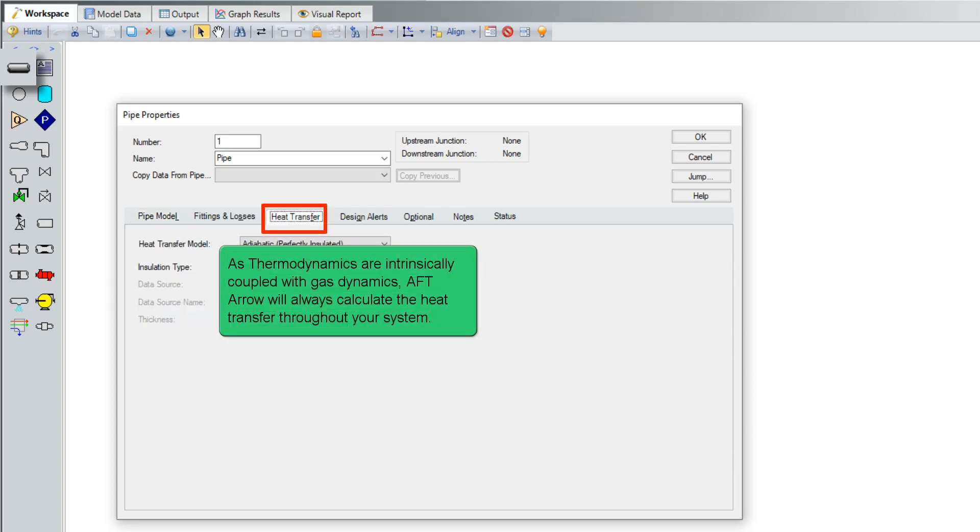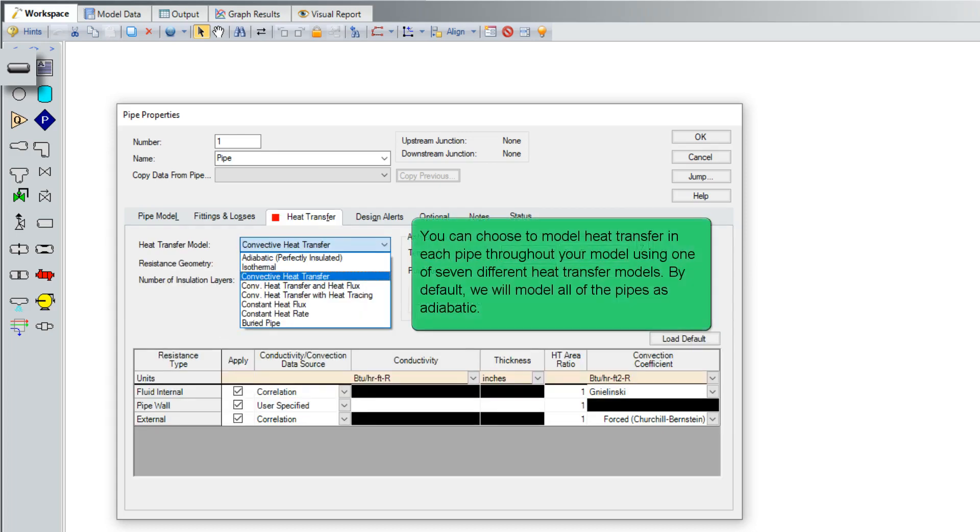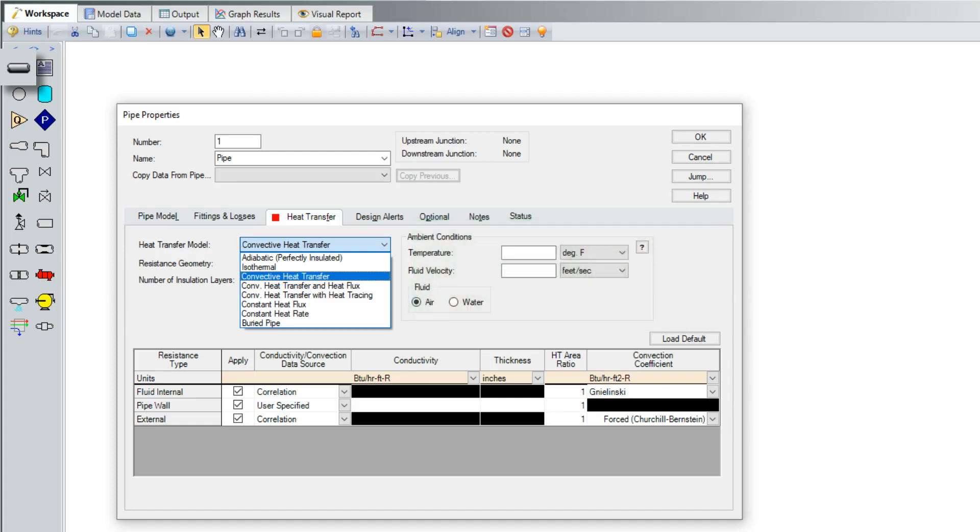As thermodynamics are intrinsically coupled with gas dynamics, AFT arrow will always calculate the heat transfer throughout your system. You can choose to model heat transfer in each pipe throughout your model using one of seven different heat transfer models. By default, we will model all pipes as adiabatic.